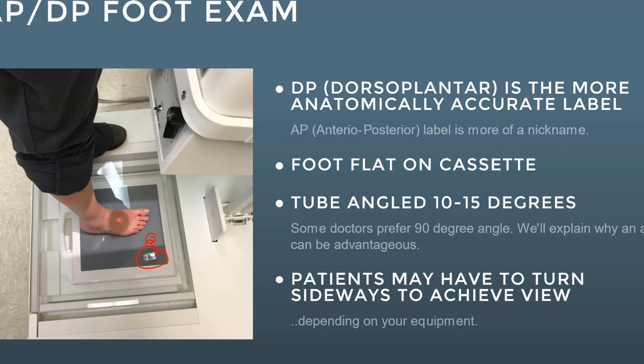The tube is angled 10–15 degrees. Some doctors prefer a straight-on shot or a 90-degree angle — don't question the doctor on that, as some prefer it. But most will go with the 10 to 15 degree angle. Note: the collimator light is simply a measurement tool showing you where the x-rays will hit — it's not required to be on the patient when you shoot. The light is controlled by the collimator dial.